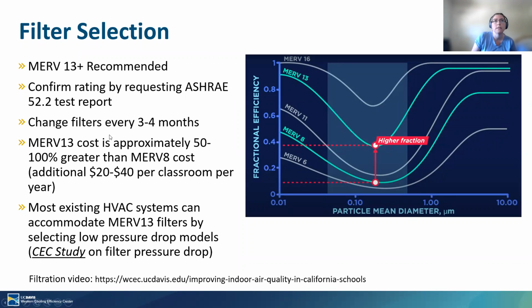And although there was a lot of discussion that school districts are concerned that their systems can't handle MERV 13, the resistance of the filter is actually pretty similar because the filter media just has additional surface area and additional pleats, and that reduces the resistance to the airstream. And so I think in most cases, any concern about that is generally a misunderstanding. I also included a link here on a study on filter pressure drop, if anybody's interested in that. And we also talk about this in our filtration video that I've linked here.